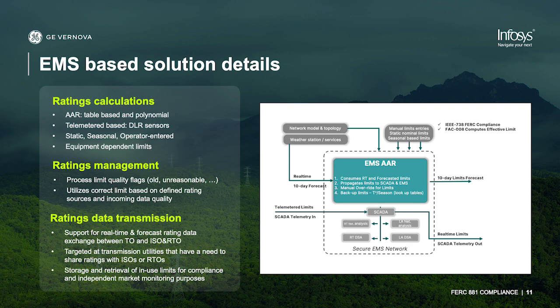It also supports real-time and forecasted rating data exchange. So with the FERC order, you have to have a real-time rating set and also forecast a rating set over your next 10 days. That has to be communicated with your neighboring TOs and your ISOs. And so we want to make sure that we're having those rating sets always in effect. And then we want to store those rating sets. I believe there's a requirement to have those ratings per the FERC order.